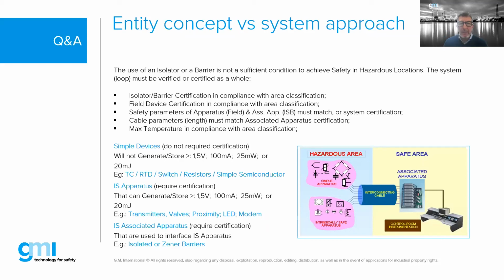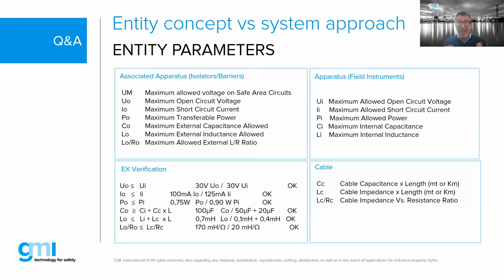So basically the concept here is that the field devices, whether simple devices or certified units, along with the associated apparatus — which are the IS barriers, whether Zener or isolated — and the wiring required, need some calculation, the same as explained earlier. You have to change this calculation if you have a combination of barriers going into the same field device. So the barrier concept is basically to limit energy, but to a level that the field device is suitable for.